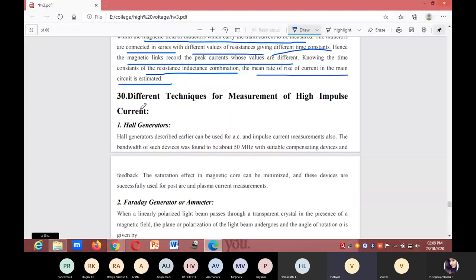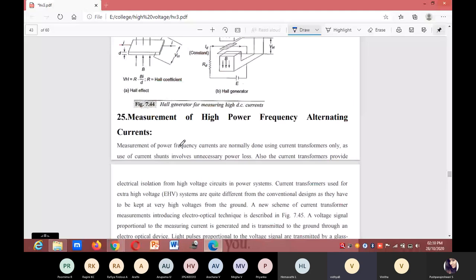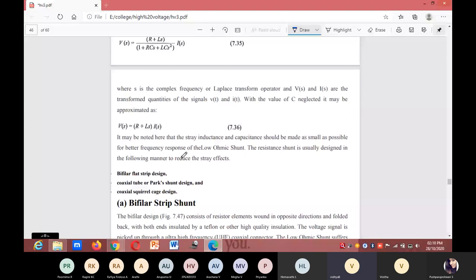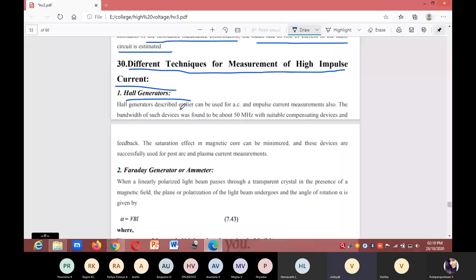Next is different techniques for measurement of high impulse current. Hall generators, which were discussed earlier for DC measurement, can also be used for AC and impulse current measurements. The bandwidth of such devices was found to be about 50 MHz. With suitable compensating devices and feedback, the saturation effect in the magnetic core can be minimized, and these devices are successfully used for post-arc and plasma current measurements.